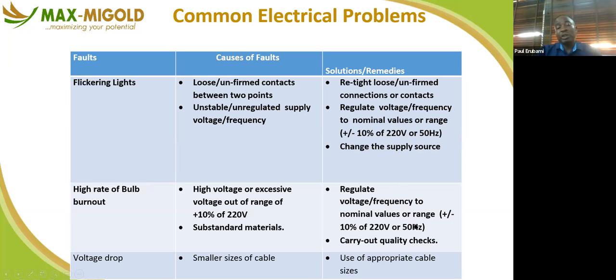Maybe you did auto tap changing, or you tap your transformer to a higher rating. When they now bring light, or you forgot to take it back to the normal, what you expect into your building is high voltage. Ensure that you do all you need to do. You may not be the one doing it, based on your introduction when we started. Ensure that your electrician or your technicians do what they are supposed to do, they check and give you record, you file your record appropriately.